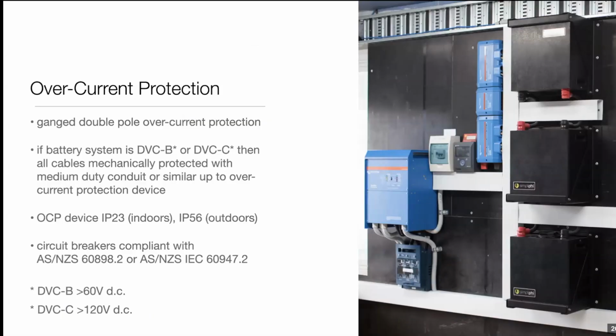So let's start looking at some of the specific clauses within 5139. Overcurrent protection, for instance, and this is actually a picture from my lab as an example of an installation of an off-grid system using SimpliPhi batteries and Victron inverters and charge controllers. You can't see the Victron charge controller in this picture. It's a requirement now that isolation of a battery system is ganged double pole overcurrent protection. In the previous AS 4086, it was possible to have individual pole protection, not ganged, but that's being changed.